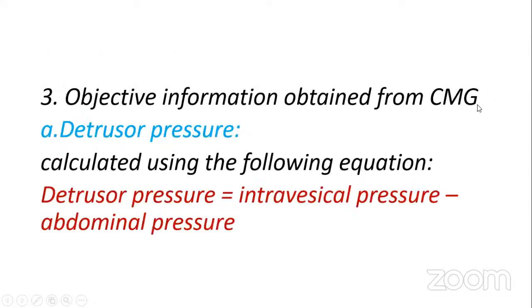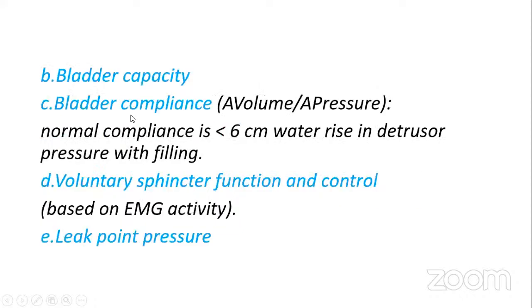Objective information obtained from CMG: the detrusor pressure is calculated using the following equation. Detrusor pressure equals intravesical pressure minus abdominal pressure. Also, through this CMG, we will check bladder capacity, bladder compliance, voluntary sphincter function and control, and leak point pressure. Bladder compliance is equal to volume per pressure. Normal compliance is less than a 6 centimeter water rise in detrusor pressure with filling.